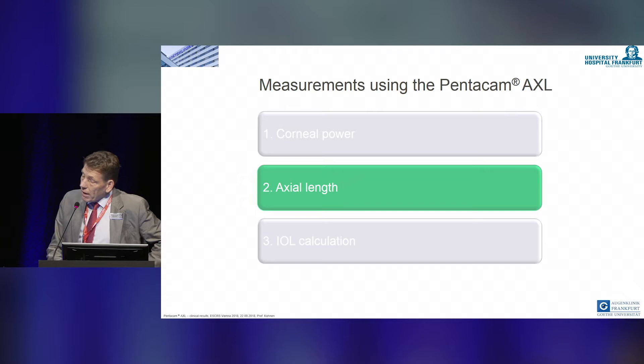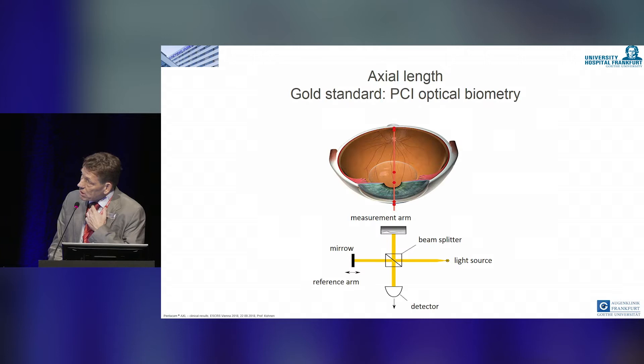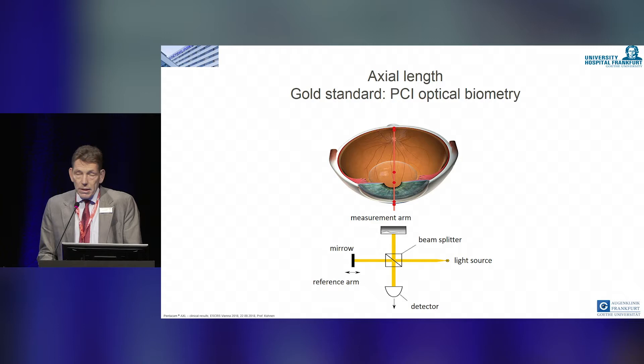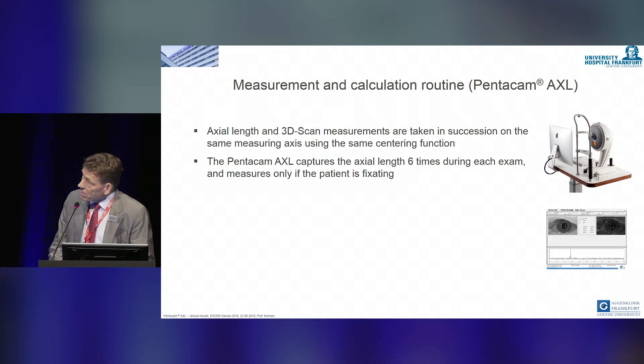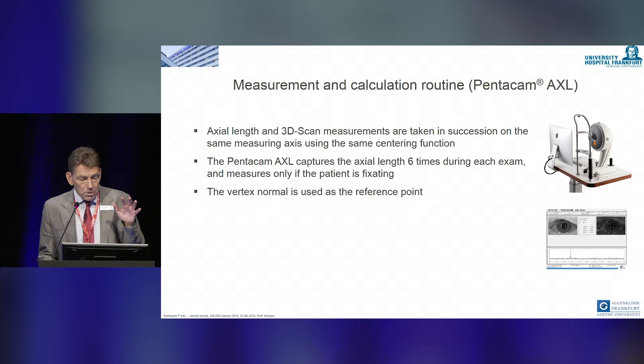Axial length now comes into play with this machine because axial length measurement is incorporated in the device. We now use as the gold standard partial coherence interferometry, and the Oculus machine has this axial length measurement incorporated. The calculation is done on a routine basis, with axial length combined with corneal measurements.